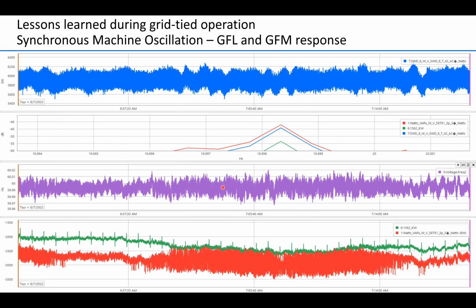That's not necessarily a bad thing. However, as a result of this kind of noisy frequency being seen at our grid following inverter terminals, they're also responding to that subsynchronous oscillation. And so it's almost like the noise produced by some of our synchronous machines driving frequency noise is causing the real power of our inverter-based resources to also look somewhat noisy. And you can see that in red right here. As compared to the grid forming mode inverter at PMRF, you can see that real power output on the same time scale, looking at the same frequency, is not as noisy.